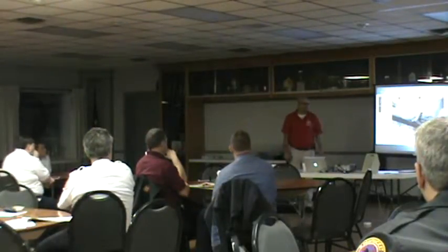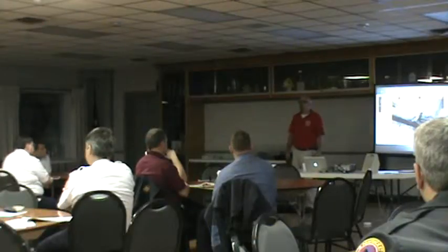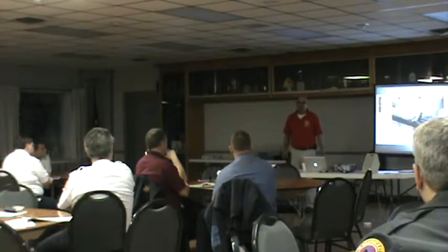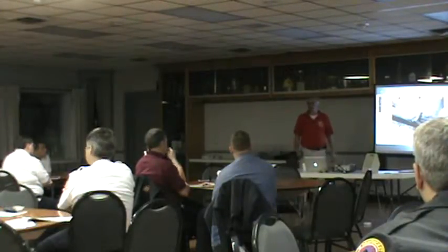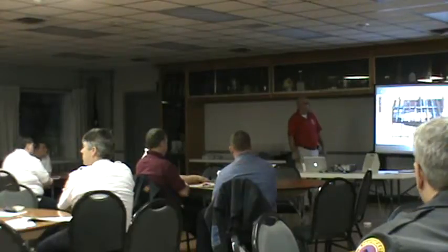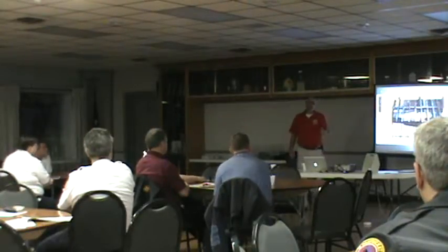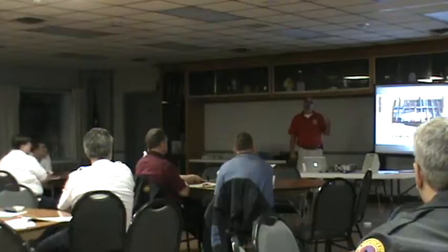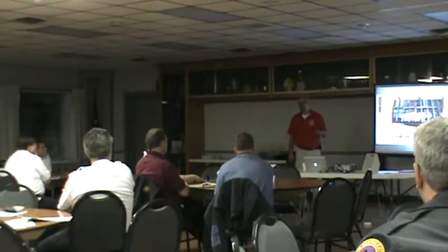ivies and stuff, this is called rust jacking. Rust jacking is when rust gets between two pieces of anything, mainly two pieces of steel, and it just starts growing rust and it blows things apart. Just like ice jacking, this is called rust jacking. This is 1 inch of rust. 25 years gets you a quarter, 50 years gets you half an inch.